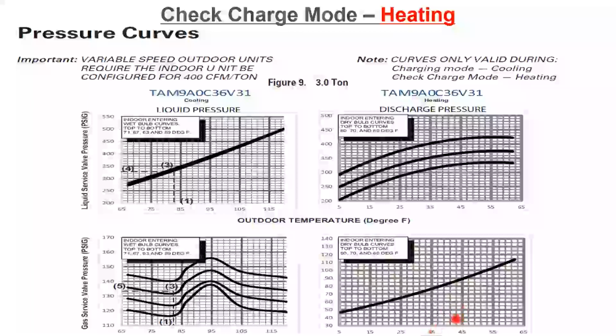So I'll slightly touch on that because I'd like to, for the guys calling in that have never used the pressure curves, once you learn how to use them, it really eliminates a lot of questions and speeds you up on your install. If it's 45 degrees out, you follow the line up to intersect. If you could see the 60, 70, and 80 degrees represents the indoor temperatures. Right here, it's 3 lines. Right here, it shows as one solid line because they're so close. So your suction, 45 degrees out, your suction should be about 90 PSI.